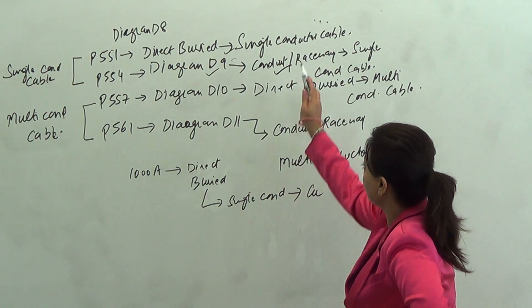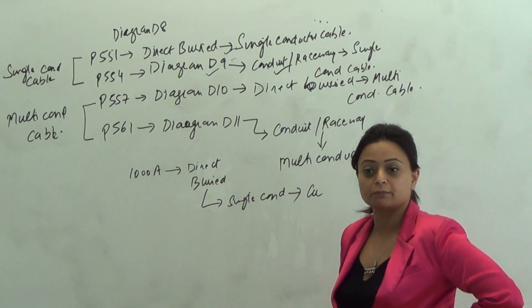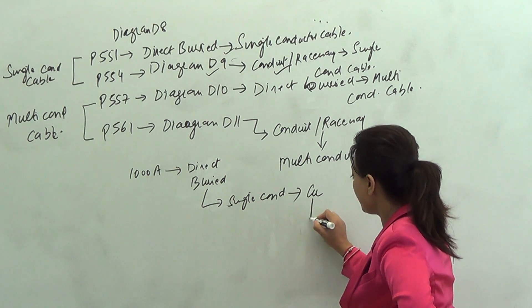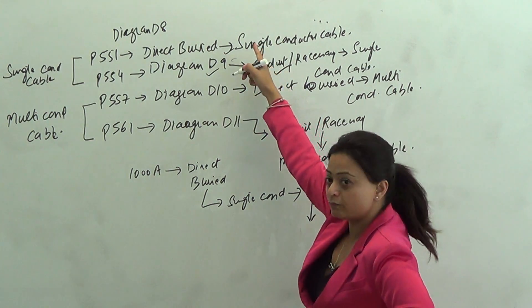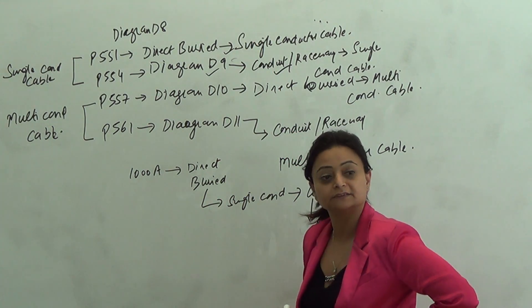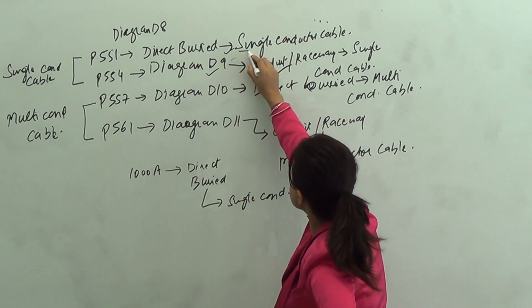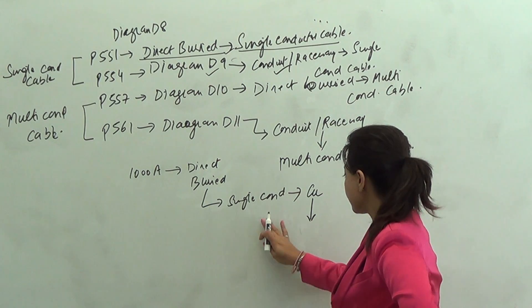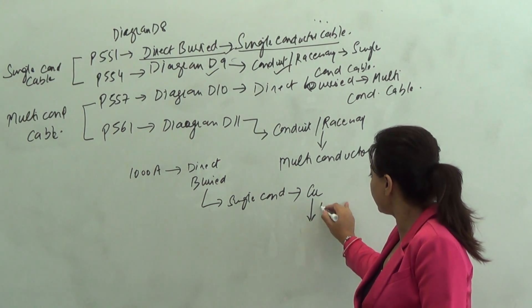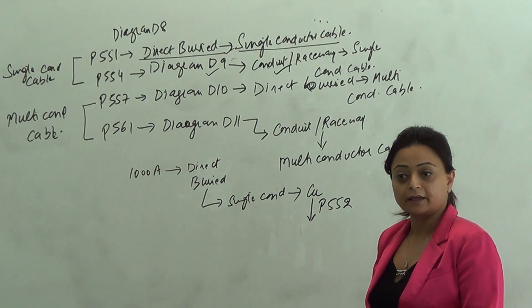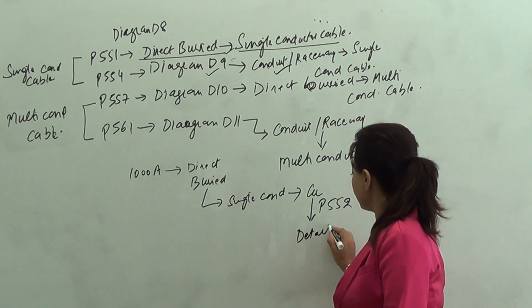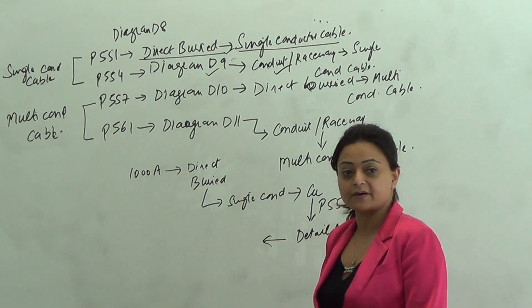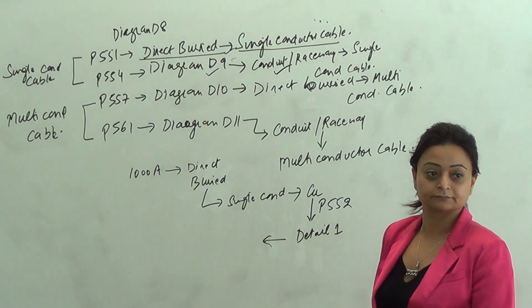Now I want each one of you to go to page 552. Tell me whether page 552 is copper table or aluminum table. Copper table. Why would I go to the first diagram? Because I am given directly buried and single conductor cable, so both conditions — single conductor and directly buried — are satisfied. Based on that, we went to page 552 because that's the copper table. Look for detail one because I am not doing any parallel run.